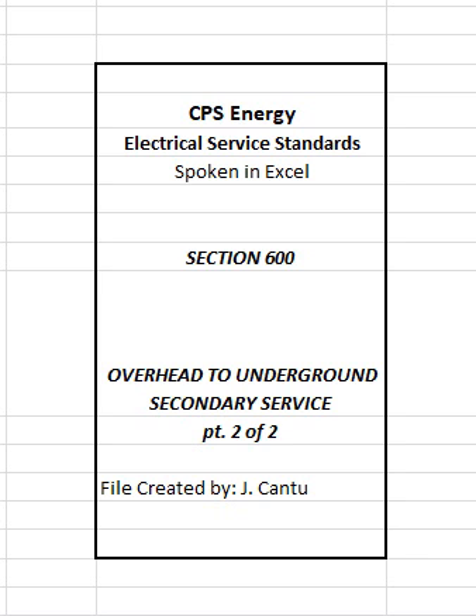Conduit sleeves shall be capped at each end with an approved PVC cap. Customer shall mark on the surface the beginning and end of each sleeve location with a stake, hub, pipe, or some other visible marker approved by CPS Energy. 4. Other utilities shall not be allowed in sleeves installed for CPS Energy.